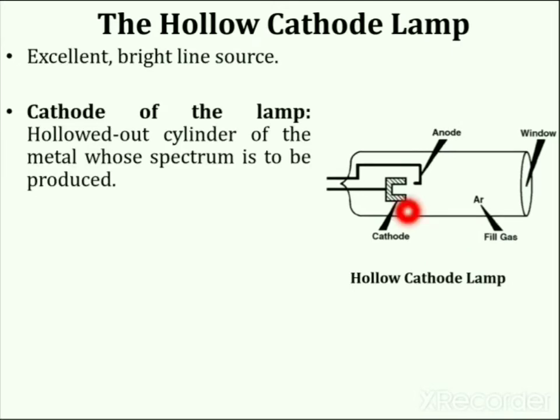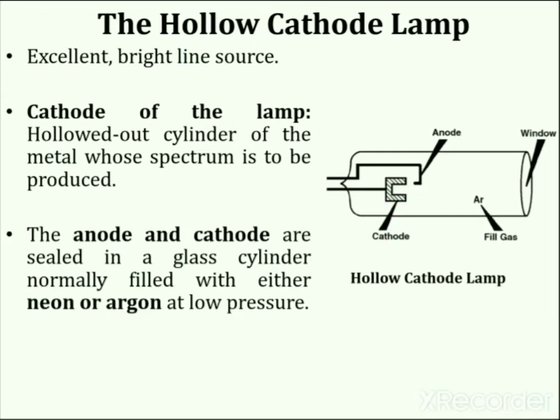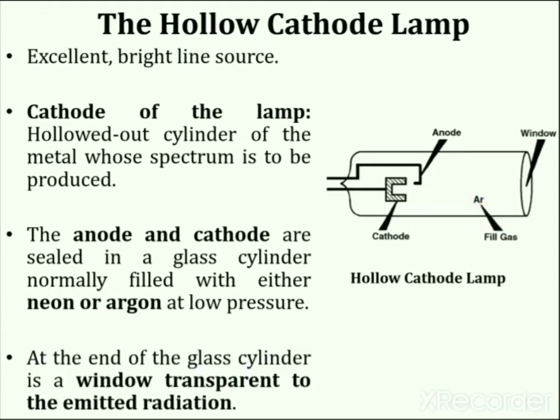The two most common line sources are the hollow cathode lamp and the electrodeless discharge lamp. The hollow cathode lamp is an excellent bright line source for most elements determinable by Atomic Absorption Spectroscopy. The cathode is frequently a hollowed-out cylinder of the metal whose spectrum is to be produced. The anode and cathode are enclosed in a glass cylinder filled with neon or argon at low pressure, with a window transparent to the emitted radiation at the end.